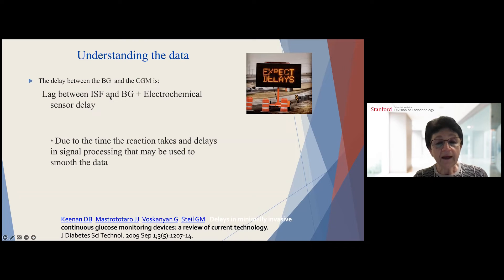It is important to keep in mind that there is a lag time between what is showing on the sensor and what you measure with a finger stick. On the finger stick we check blood glucose, but on the CGM device we check interstitial fluid glucose. There is a lag time between interstitial fluid and blood glucose, plus an electrochemical sensor delay — all of which delays the reading by about 10 to 15 minutes on average, including signal processing used to smooth the data.